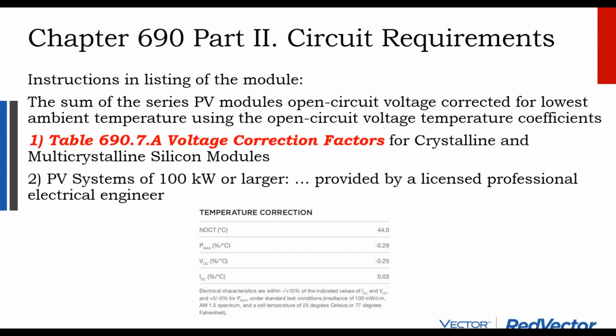National Electric Code is fudge factors so that electricians who aren't engineers can do the design work in a safe manner. But electric code almost across the board allows an engineer to step in with a calculation to say, I'm going to do the math for real, and that's going to give me a little bit less of a design constraint than using the fudge factors.